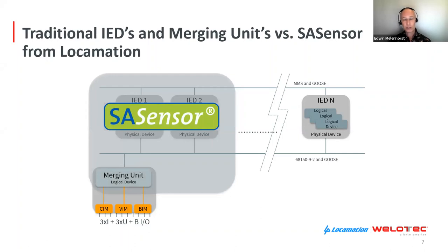SASensor has been developed over 15 years ago and is operational in several countries in over 200 substations. SASensor is a CPC system, centralized protection and control, and one could say that it has virtualized the process bus and station bus, as well as much of the functionality present in current substations. However, SASensor is a proprietary solution, and it's not very easy to integrate with third-party IEDs because it doesn't talk sampled values, GOOSE, or MMS.